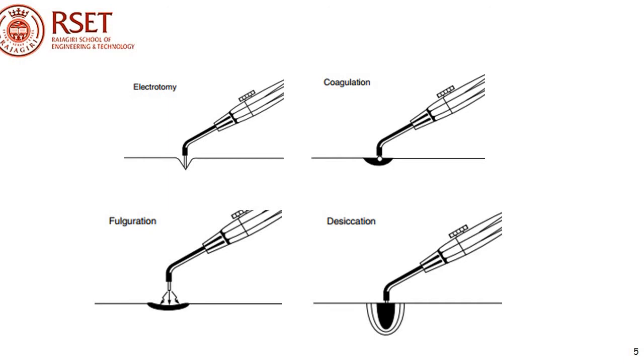Electrosurgical coagulation of tissue is caused by the high frequency current flowing through the tissue and heating it locally so that it coagulates from inside. The coagulation process is accompanied by a grayish-white discoloration of the tissue at the edge of the electrode. The term fulguration refers to a superficial tissue destruction without affecting deep-seated tissues. This is undertaken by passing sparks from a needle or a ball electrode of small diameter to the tissue.